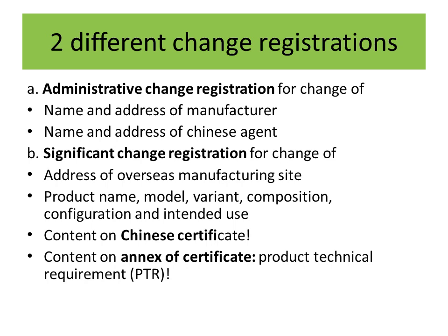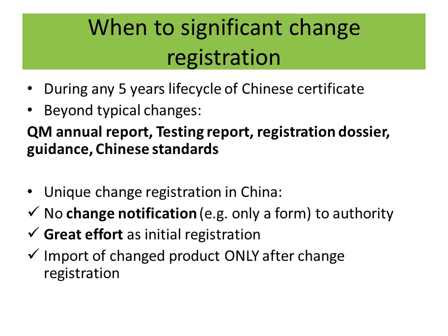change. Actually, you apply for a change registration only if you want to market this change of product on the Chinese market. An annual quality report is to be submitted to the authority as of 2023, which requires some of the product changes introduced in the former slide and some quality changes. Don't ignore other triggers for change registration, such as change of critical components submitted as local Chinese testing, revised shelf life validation as an important registration chapter in the dossier, newly issued guidance and obligatory standards.